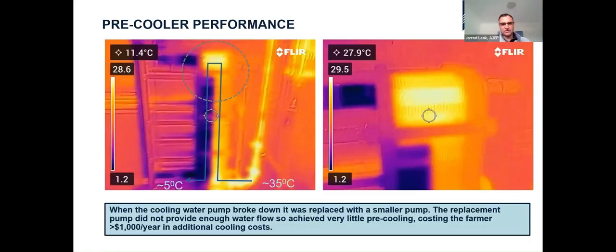And that's exactly what I saw at a farm last year. This is a thermal image of a double bank heat exchanger. You've got your pre-cooling section shown here in the lighter color where it's hotter, and then a glycol or ice water chilling section in the second part of the milk cooler. We put the temperature thermometers on and saw the cooling water coming in was around 16 degrees, but we noticed the milk cooling being done by that cooling water was very little.